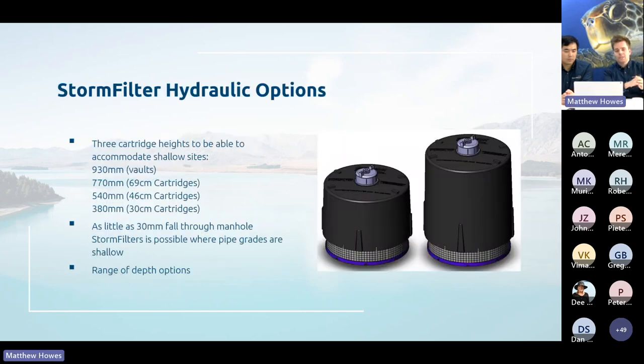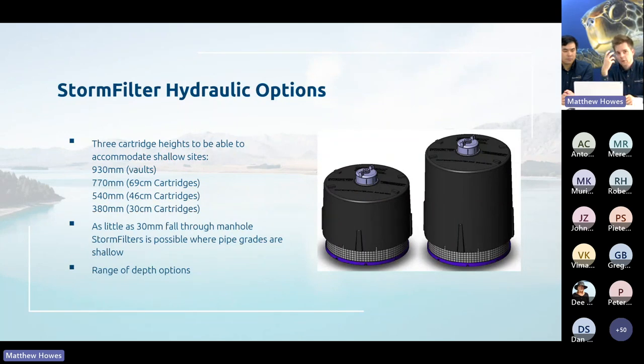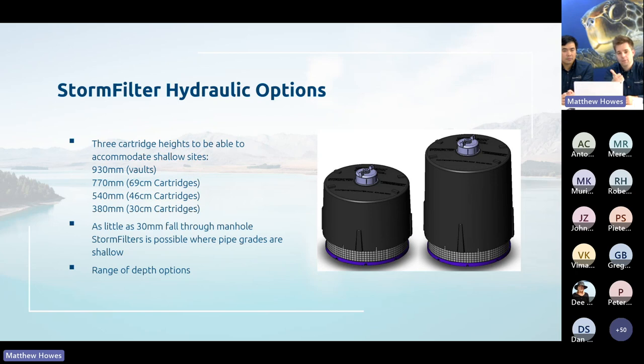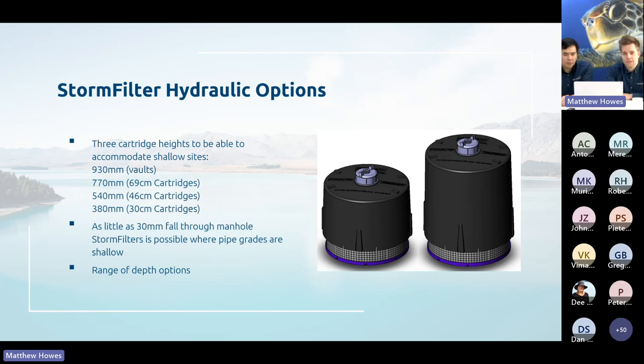There are many places within the Storm Filter where there are individual head losses through the system. We have a range of driving head options: 930mm for our vaults, 770mm, down to 380mm depending on cartridge height within manholes. These head losses account for all losses through the system — the depth of flow in the outlet pipe, losses through the restrictor disk, the under drain, and the cartridge. There is a lot more to understanding the actual head losses through the system than just knowing what driving head is needed for the float to pop.